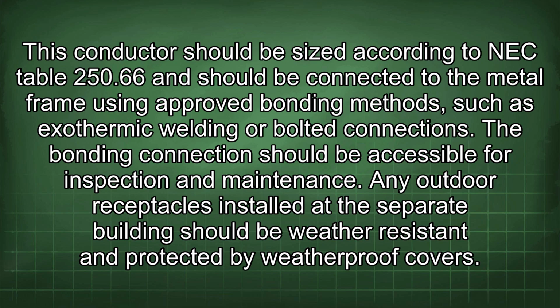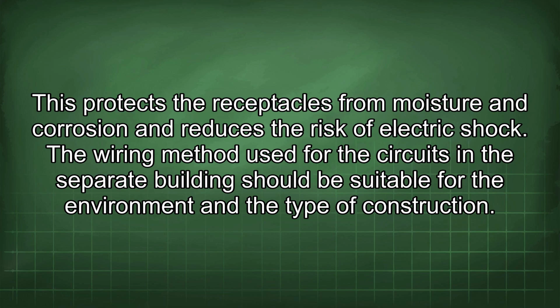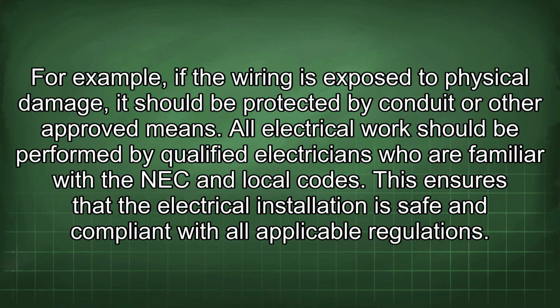Any outdoor receptacles installed at the separate building should be weather resistant and protected by weatherproof covers. This protects the receptacles from moisture and corrosion and reduces the risk of electric shock. The wiring methods used for the circuits in the separate building should be suitable for the environment and the type of construction. For example, if the wiring is exposed to physical damage, it should be protected by conduit or other approved means. All electrical work should be performed by qualified electricians who are familiar with the NEC and local codes. This ensures that the electrical installation is safe and compliant with all applicable regulations.